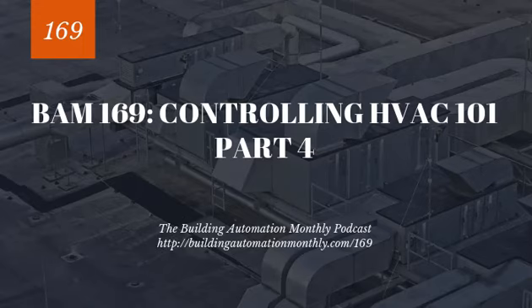So it's really simple, right? Hot water boilers, we get our hot water supply and return temps, our primary pump command and status. We want to make sure we have flow. We enable the boiler, we turn on the pump, make sure we have flow, and then control our hot water supply set point. That's pretty much all there is to it when it comes to single boiler control.